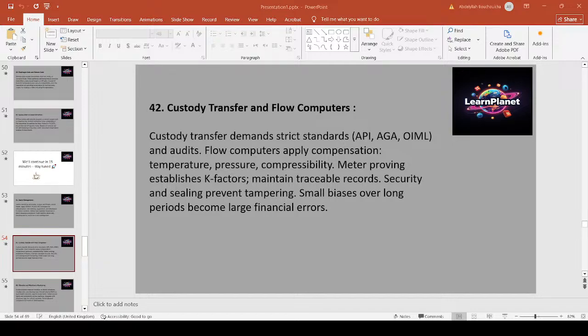Custody transfer is high stakes. Follow API, AGA, and OIML standards and keep auditable records. Keep meter proving data and K factors. Flow computers apply pressure, temperature, and compressibility corrections, calculate mass or corrected volumes, and handle pulse inputs from meters and provers. Seal and secure flow computers and maintain physical and cyber protections to prevent tampering. Example, for gas sales, use an AGA-approved flow computer with scheduled proving and traceable correction factors.